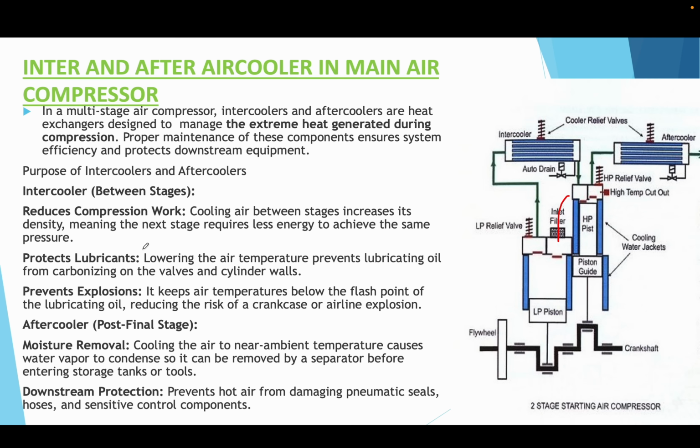Second most important point is that it protects the lubricant. The air which is coming out after the cooler is cooled, so the temperature is lower. Because of that, the lubricating oil between the HP piston and liner is prevented from getting burned out, and hence the overall running hour of a machinery is increasing, because there will be an efficient boundary lubrication which will increase the life of a running compressor.